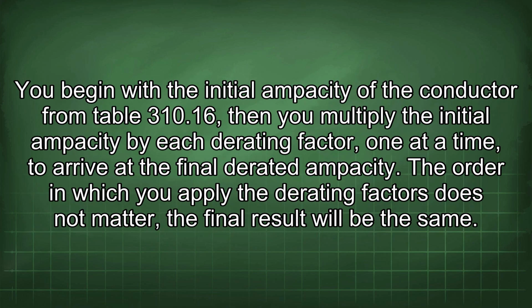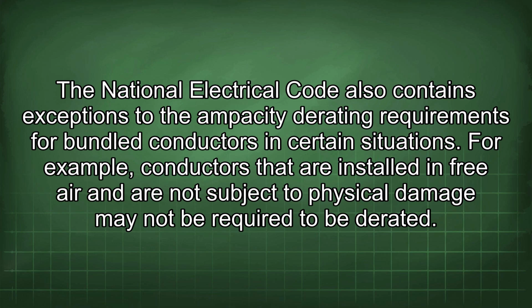You begin with the initial ampacity of the conductor from table 310.16, then you multiply the initial ampacity by each derating factor, one at a time, to arrive at the final derated ampacity. The order in which you apply the derating factors does not matter, the final result will be the same. The National Electrical Code also contains exceptions to the ampacity derating requirements for bundled conductors in certain situations.